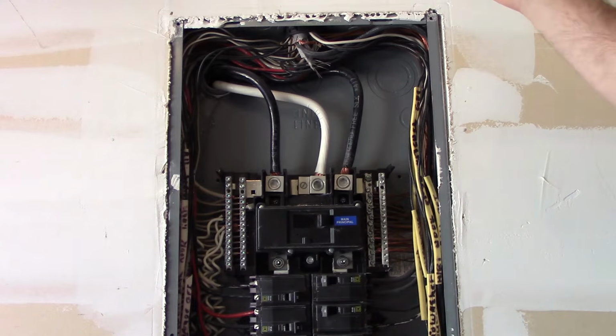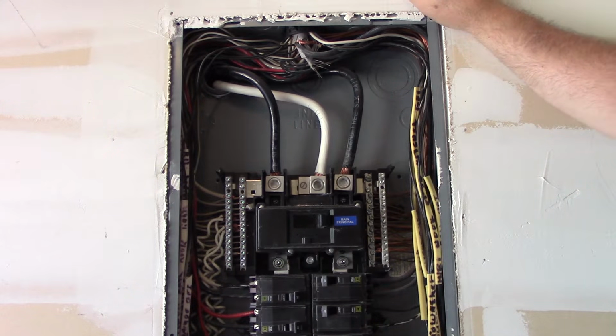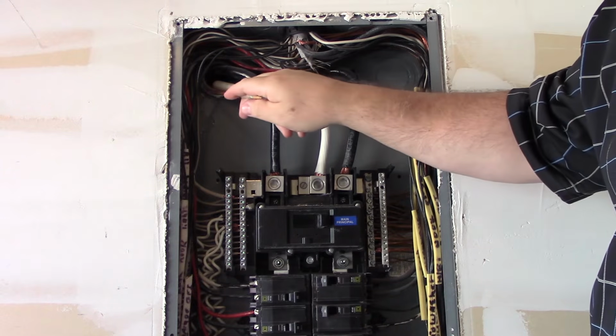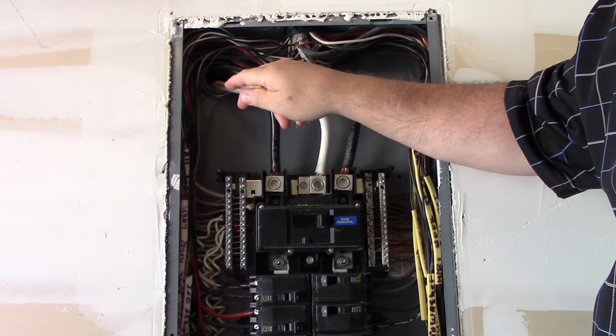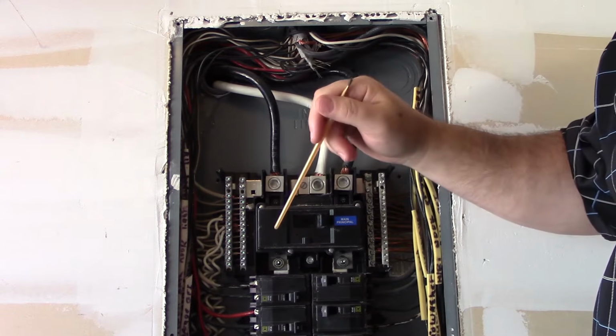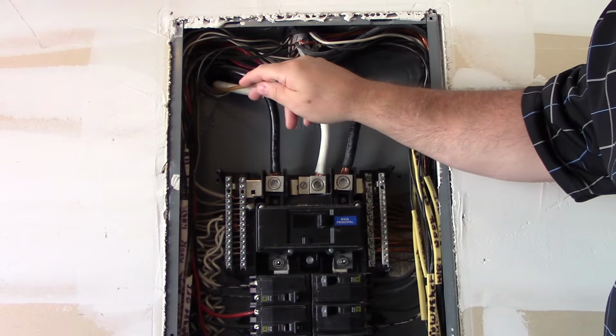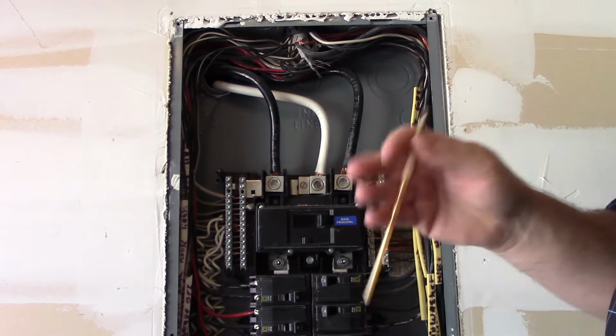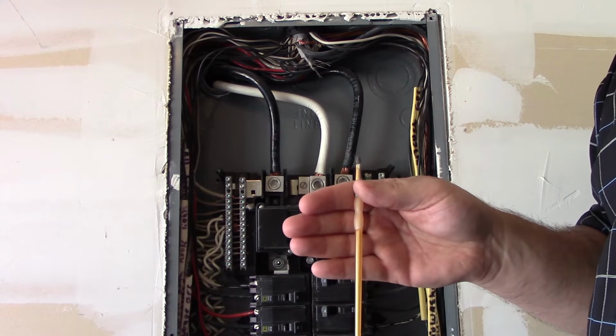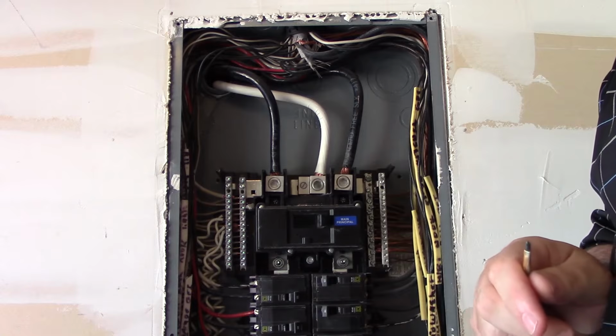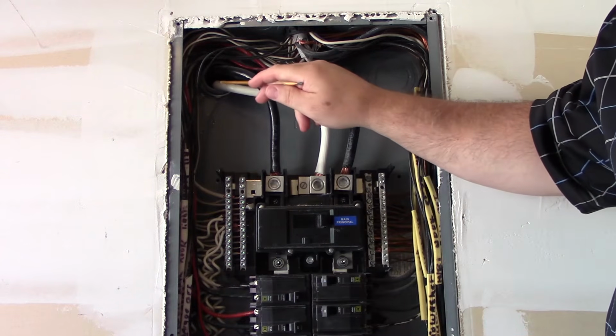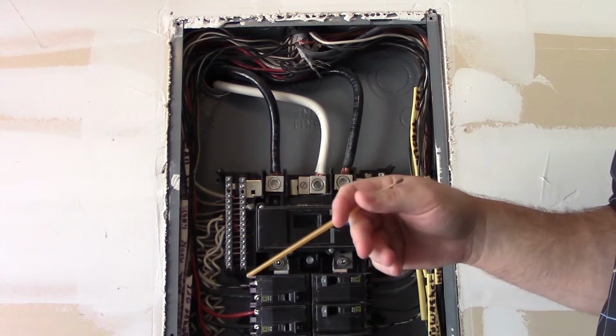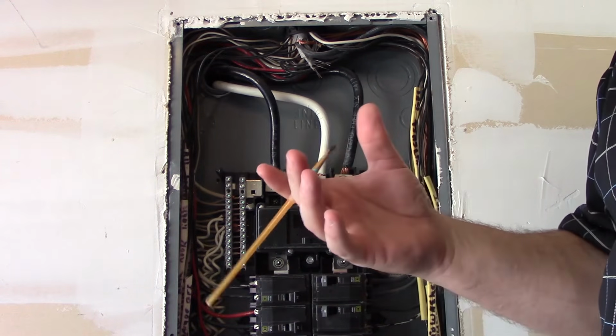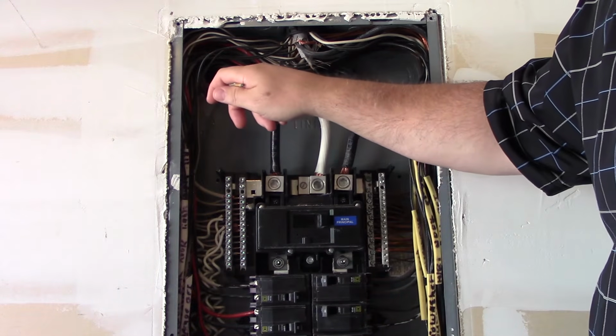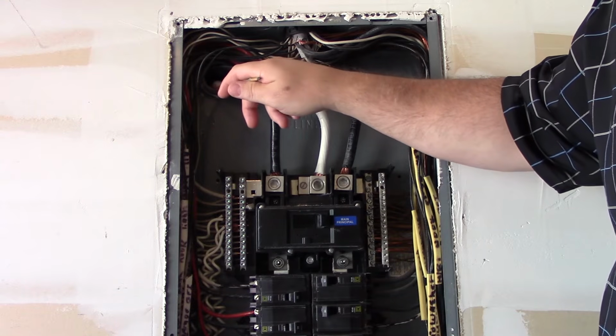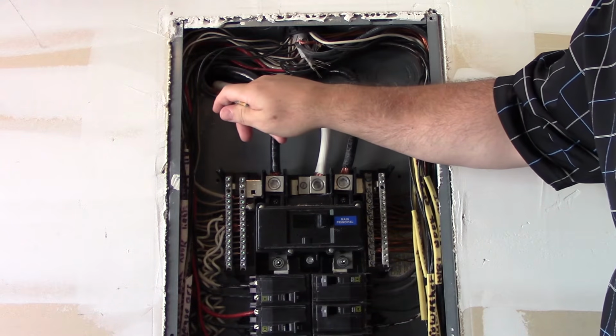Okay, the next thing we want to do, the first thing I like to do, is to start with how it comes in. So here it comes in through, it appears to be, a non-metallic nipple back to back with the meter that's on the outside. So one thing I noticed is that these conductors are obviously larger than a 4 gauge. So in accordance with 300.4(G) of the National Electrical Code, any conductor that is 4 gauge or larger would have to have a bushing on the actual raceway as it comes in, in order to protect these conductors from being cut on this sharp edge here.